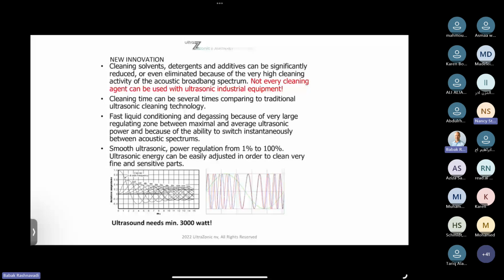Now, the new innovation with this device, as I told you, is that we have different frequencies and so on. But also when you have a really good working ultrasonic cleaner, then you need less detergent because you can really count on the productivity of your ultrasonic, okay? That also means that you cannot put just any cleaning agent in an ultrasonic equipment, because it's all about your cavitation bubbles. Your cavitation bubbles just need the support of your cleaning agent and nothing else. Now, of course, if you have a good ultrasonic device, you can really minimize the cleaning cycle. You can minimize it to 3 minutes even. Okay. Now, the first thing that you have to do in the morning is to degas your cleaning sink.